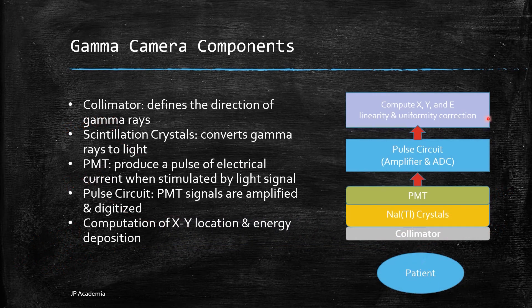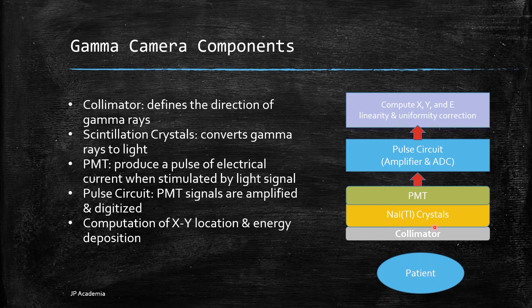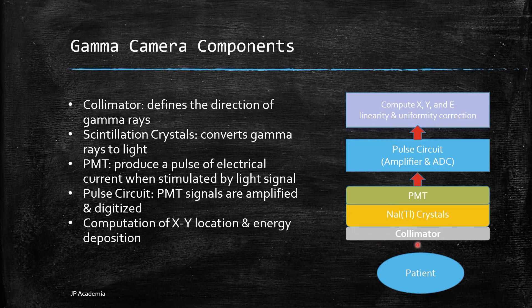So, I have this illustration. The patient will release gamma rays, and the first layer here is the collimator. The collimator is composed of a lead plate with large number of holes. It controls which gamma rays are accepted and it defines the direction of gamma rays. This will produce a gamma distribution projected to the scintillation crystals.